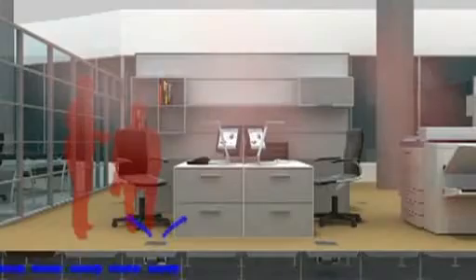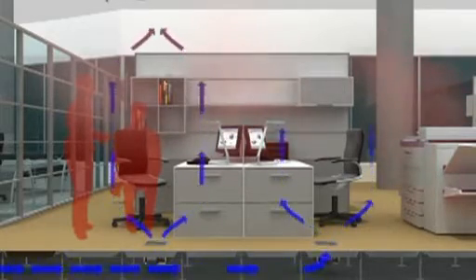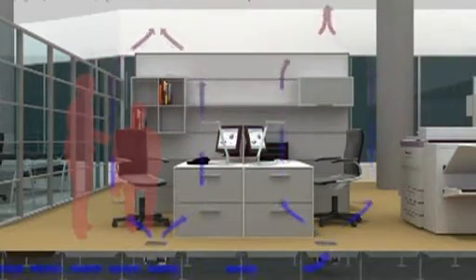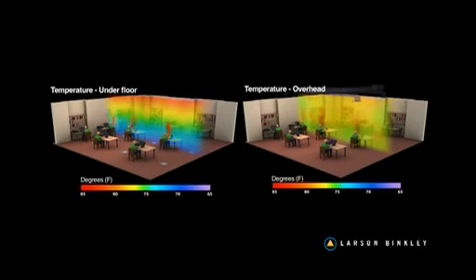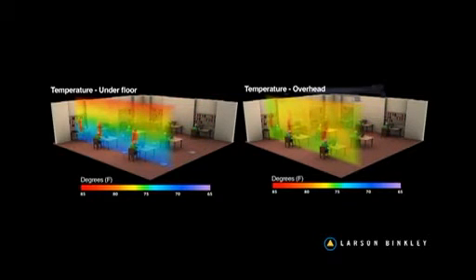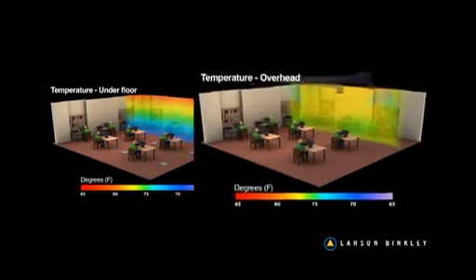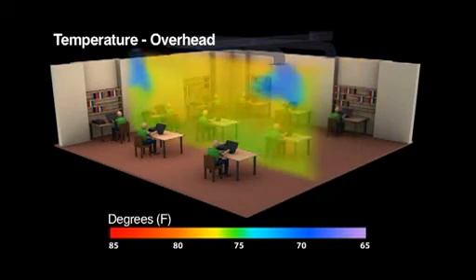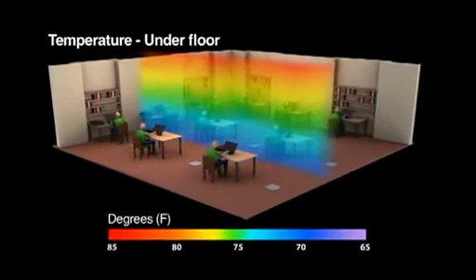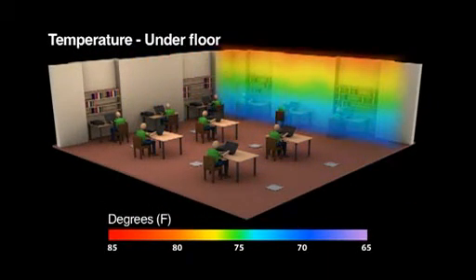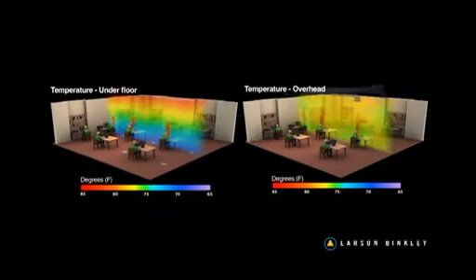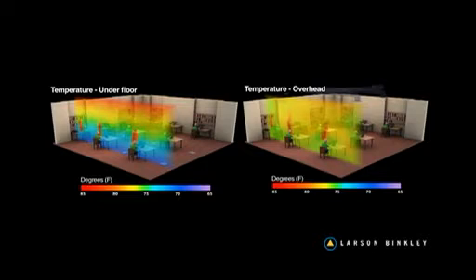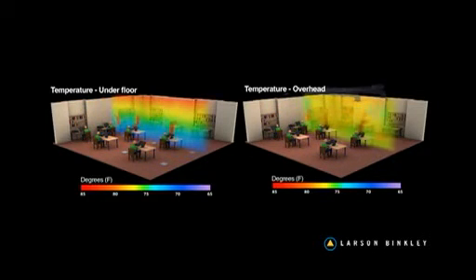If you think about the way heat rises off the pavement — heat waves — that's an easy mental depiction of what happens with heat sources in a room. Heat will rise from the source, and if left undisturbed, it will rise out of the occupied space, stratifying near the ceiling. These graphics illustrate a typical temperature profile of an underfloor air distribution system and a ducted overhead system. The redder the color, the hotter the temperature. The mixing system is doing what it was designed to do, constantly mixing up the heat and contaminants in the space. The underfloor air system is allowing heat to stratify in the unoccupied zone, shown as a redder color toward the ceiling. You can see the heat plumes are more pronounced on the underfloor side of the profile, and that the conditioned air is more concentrated where the people are in the space.